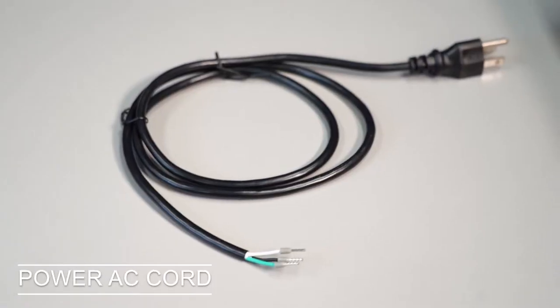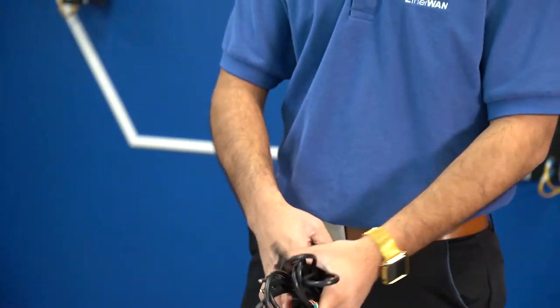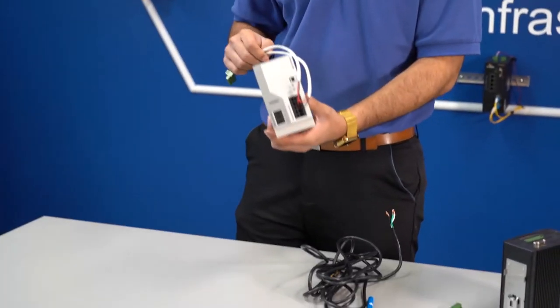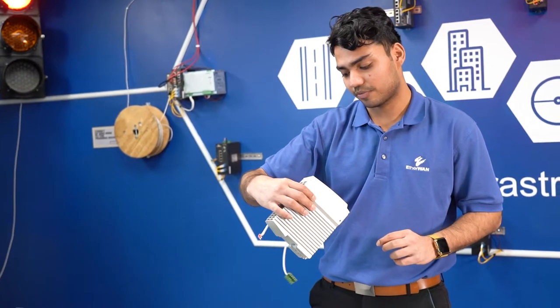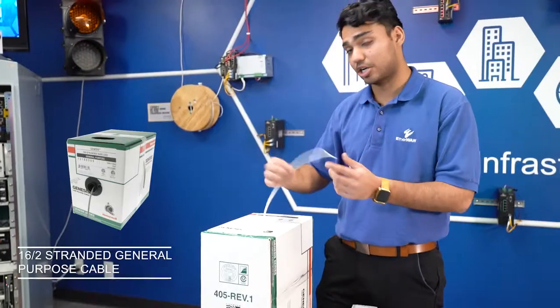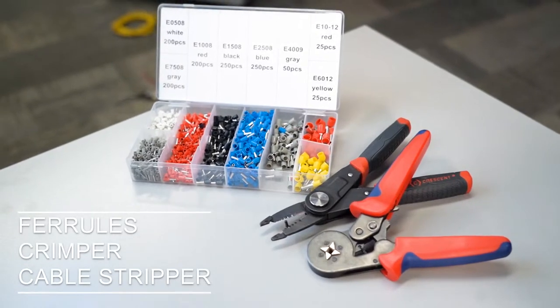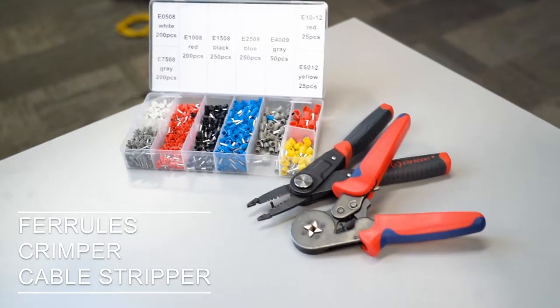The things that we'll need are here: a power AC cord that has three prongs on one side and three cables on the other side, a screwdriver, and a power supply. For this video, we'll be using the Phoenix Contact Trio Power, a general purpose 16-gauge stranded cable, and some ferrules, crimpers, and a cable stripper. Let's get started.